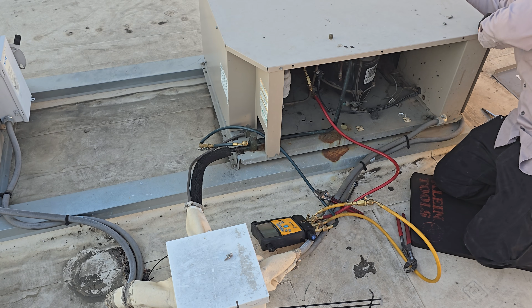Everything's right down in here, so we're working on getting the equipment on the roof pumped down right now so we can start unhooking everything. All that we're doing is pumping down all the refrigerant into the liquid line receiver. We're going to shove the gauges in the unit and then we'll recover the gas down on the ground. It makes it a lot easier.